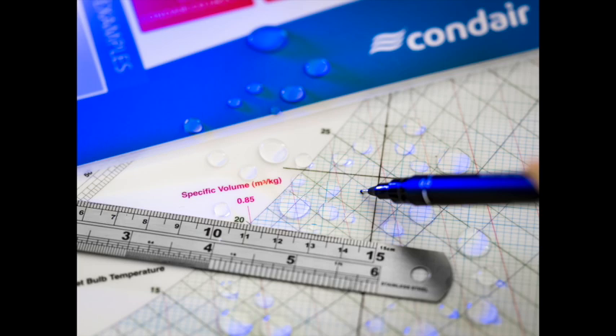But we do have webinars explaining this calculation on our website, condair.co.uk, along with downloadable copies of the psychrometric chart itself. And we're always happy to perform these calculations for anybody considering a humidification project. And for anyone wanting this, what was it you said was needed? The air condition information? Yeah, for an accurate sizing, we need the temperature and humidity of the air at its starting condition. This is when it holds the least amount of water and is typically the coldest possible outdoor day in the winter, which for the UK mostly tends to be -5°C at 100% saturated.